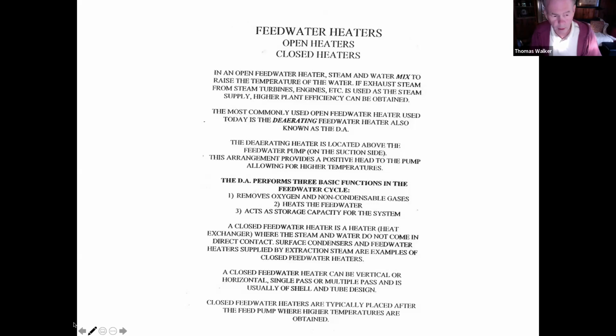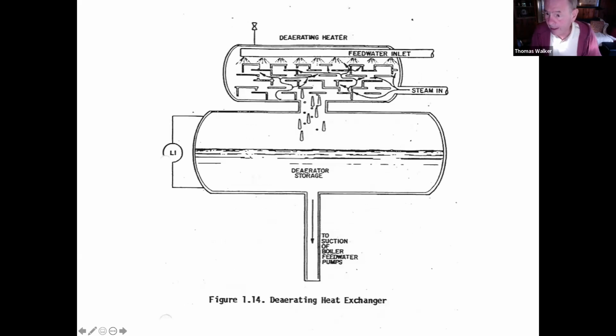What they typically ask second firemen is this: what 3 indicators would you like to have on the DA to help you operate it properly? Well, you'd like to have a level indicator that will tell you how much water is in the storage section. This is critical because if you run out of water here, what won't get any water? The boiler. Yeah, the feed pump and the boiler. This is the sole source of water for the boiler.